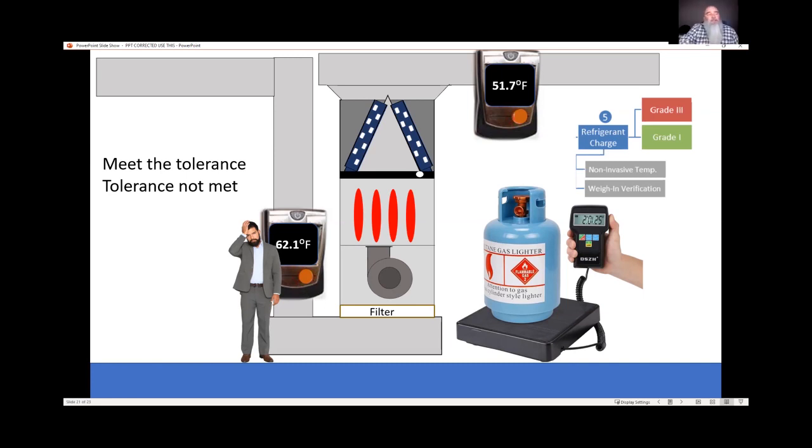Yeah, and if somebody wanted to do something so that they didn't have to do anything after they did a proper evacuation, which is not part of the standard, but we are always going to encourage that. The manufacturers generally, and I'm going to say 95% of the time, what I'm going to say is accurate, put enough refrigerant in the systems for the indoor and outdoor section and 15 feet of tubing connected. So if we stay there, there's no additional charge added. We're just going to document no additional charge added, and the rater can get a tape measure out, or I'm sure they can look at something and say, yeah, it's 10 or 15 feet. Then we start getting into, and again, this is a generalization, it's usually going to be somewhere around 0.3 ounces per foot of connecting tubing. And then we're going to adjust for that. We're going to do that with the scale.